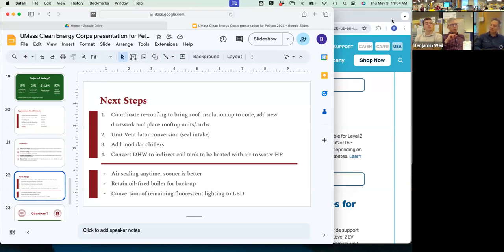And then I think I get this, but again, I'm not a building expert. You're using the existing heating system as a heating and cooling system with the air to water heat pump, and then blocking off the exhaust component of the current ventilation system and adding the intake. The current exhaust pathway moves from an exhaust fan, where you just throw it all away, to the rooftop units, where you can recover the energy.